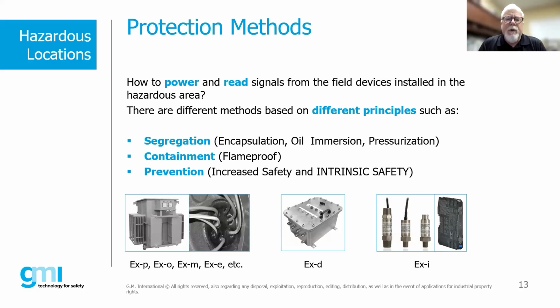And then finally, prevention, which we really categorize increased safety and intrinsic safety into. Increased safety is commonly used for junction boxes, terminal boxes, where we're limiting the heat and trying to minimize any potential spark taking place. Intrinsic safety is a concept where we're limiting the amount of energy that could potentially be released in the form of an arc or spark within the hazardous location.